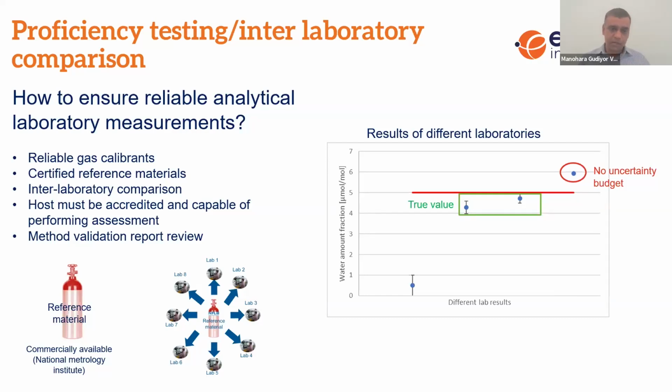There are simple steps. One needs to use calibration standards, and those calibration standards have to be certified. Then you need to have an inter-laboratory comparison, and the host doing this inter-laboratory comparison has to be accredited and capable of performing the assessment independently. And then there should be a method validation report. If you look at the bottom of the slide, I'll give an example.